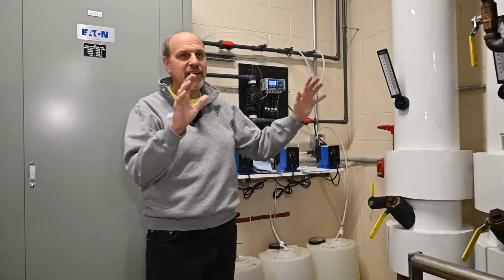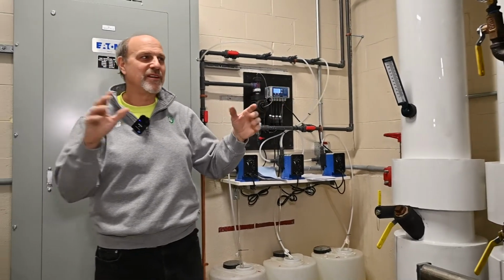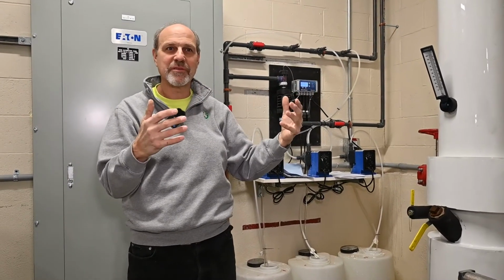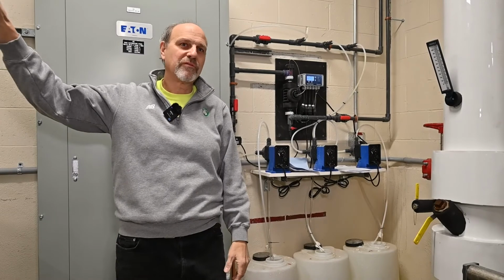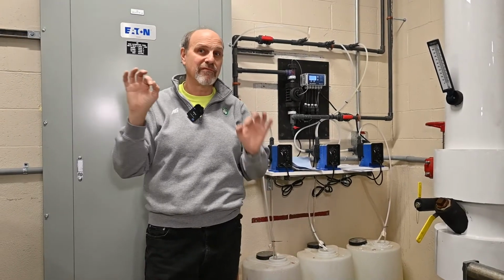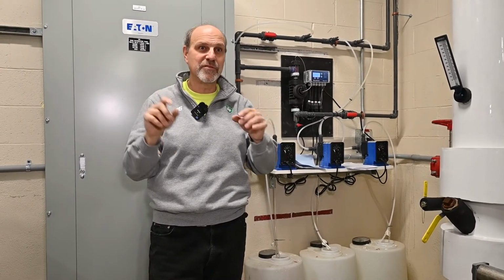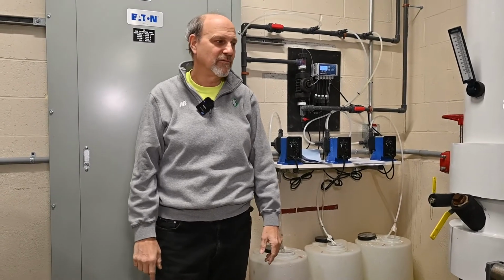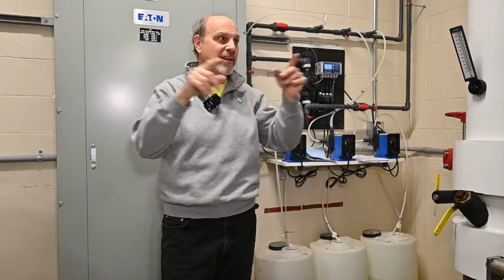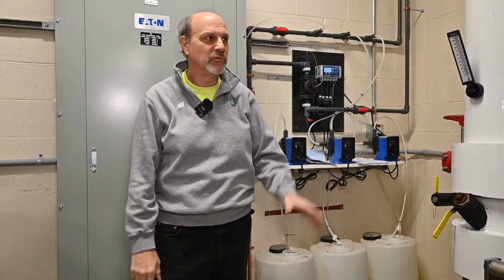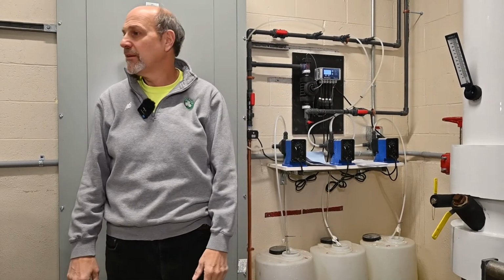As I say, there's plenty of gauges and thermometers that you can see and read visually for pressures and temperatures, but you'd really probably work from Carl's automation system, because that really is telling you what everything is doing down to the real nitty-gritty. So that's much more accurate than just reading the gauge here. But we put these on as a visual as well.